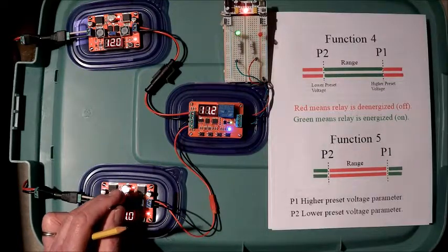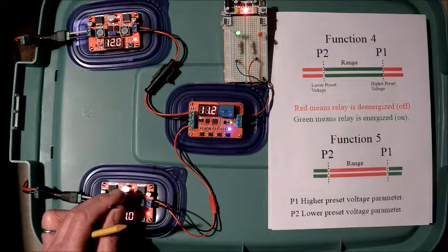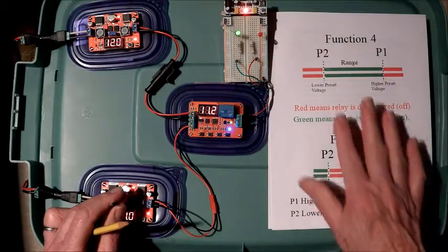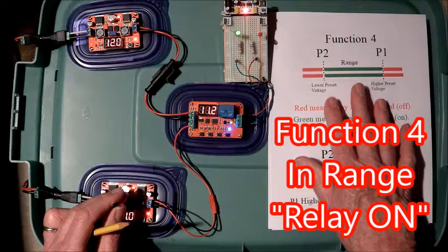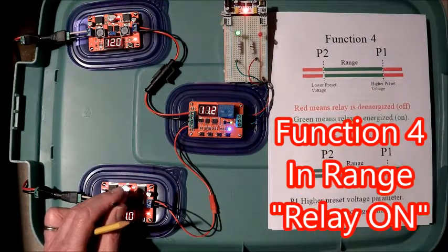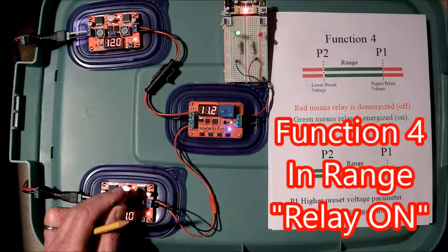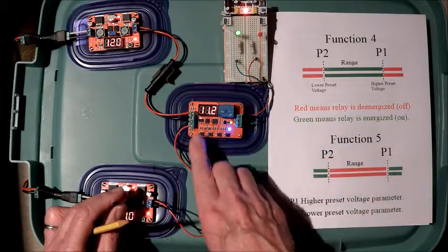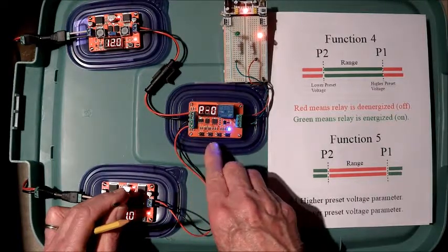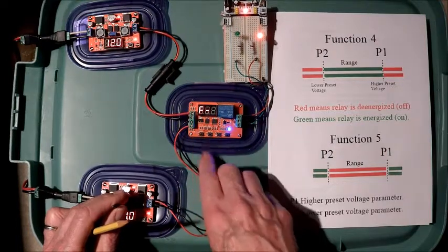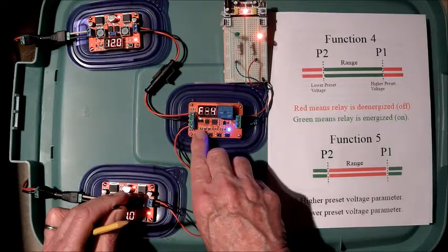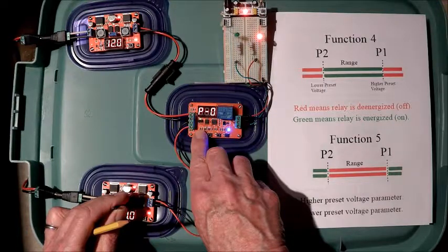Function 4. Function 4 and Function 5 are range functions. If the preset values are establishing the range, then if you're outside of the preset values, higher or lower, the relay will be off on Function 4. If you're within the range of the preset value, the relay will be on or energized. Coming out of Operational Mode. Go to the Function by hitting the Set button again. We're at Function 3. We're going to go to Function 4. Save that. Go back into Operational Mode.